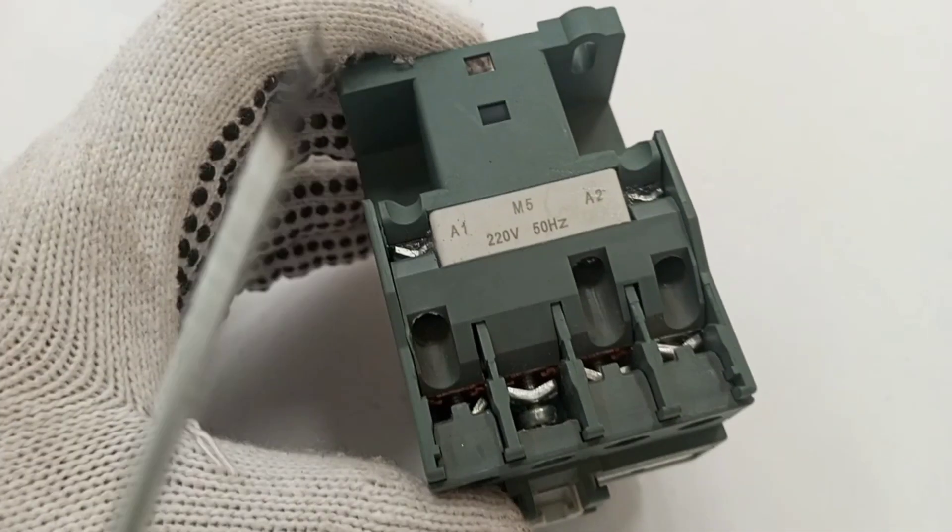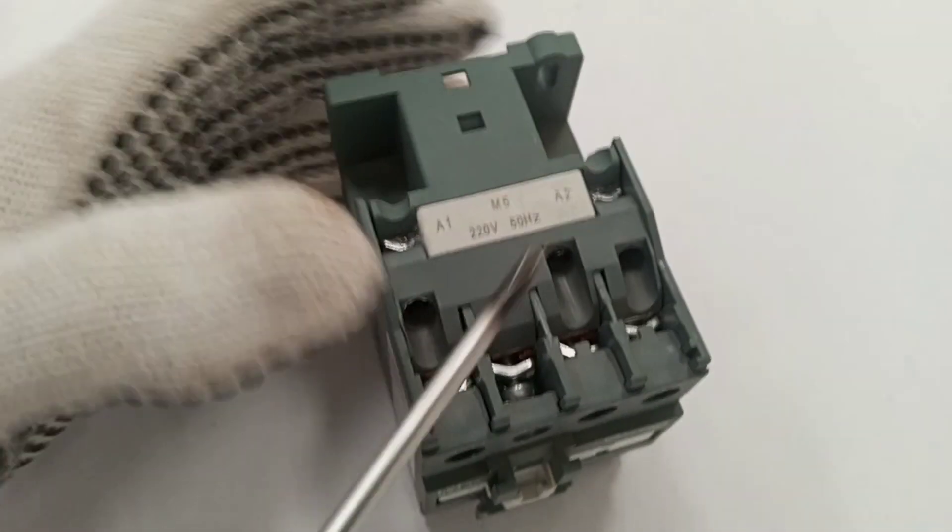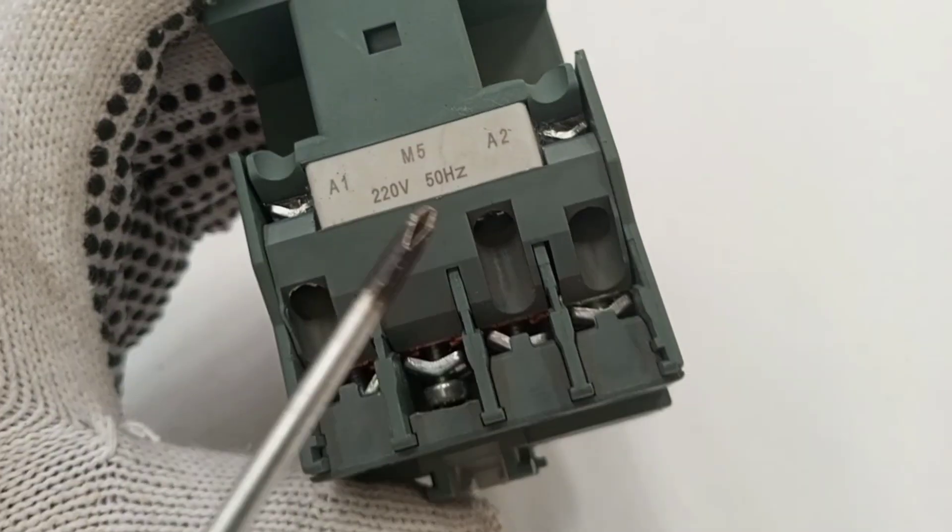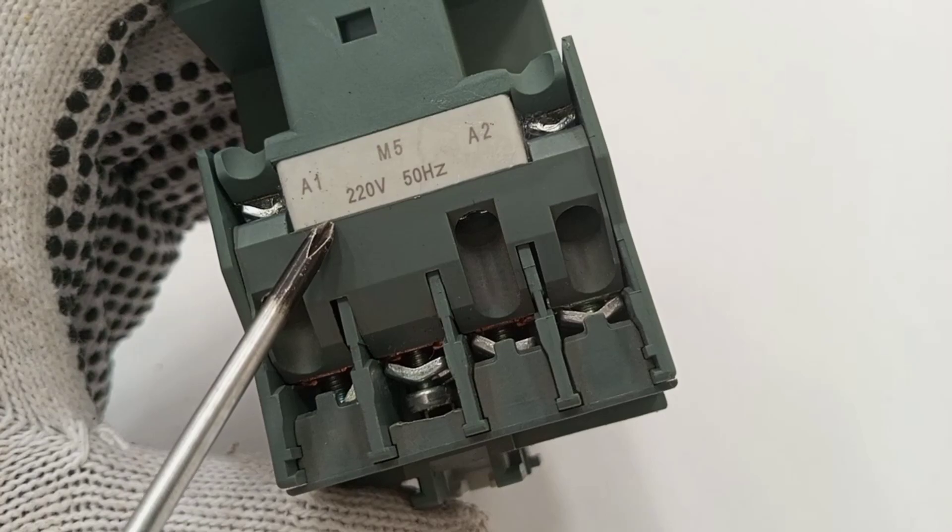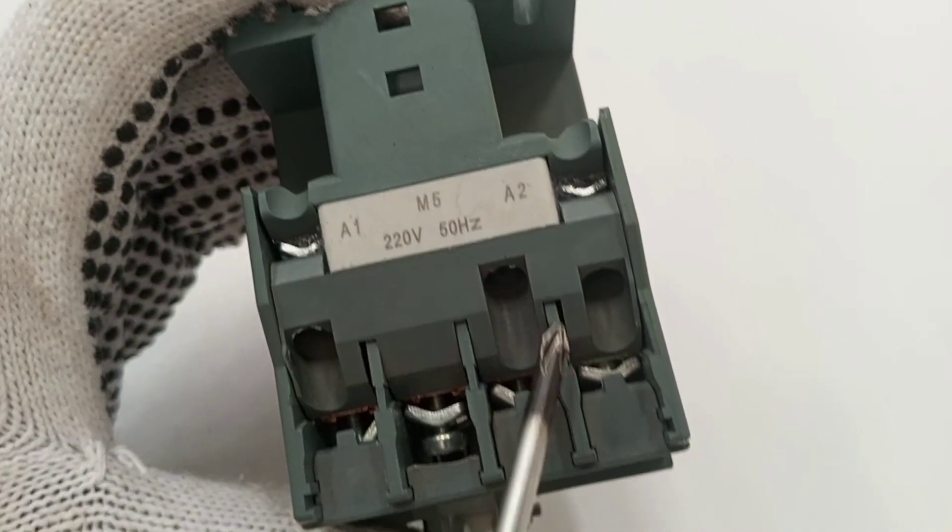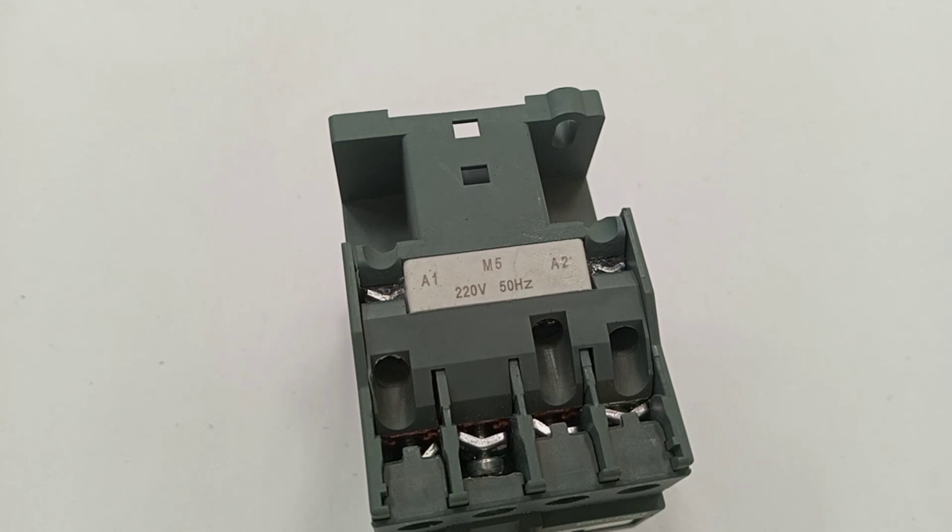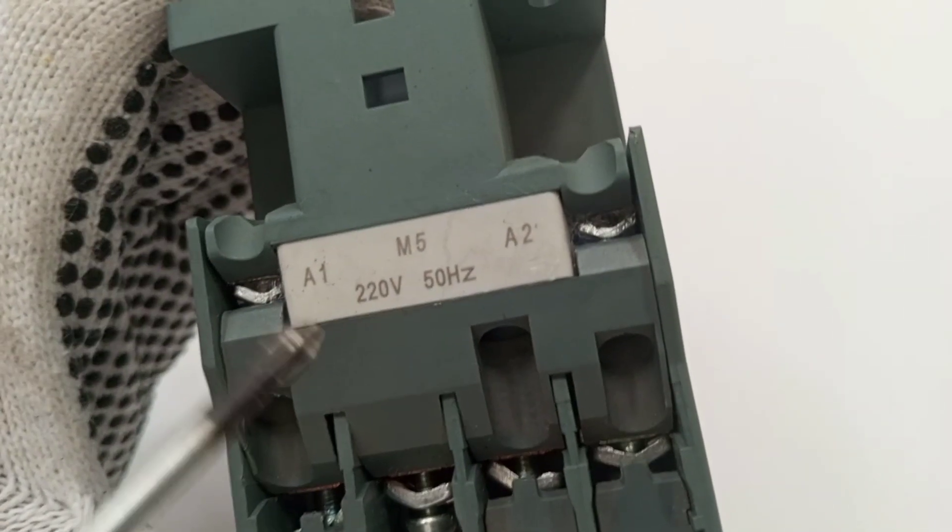There is no one standard voltage for contactor coils. The contactor coil can be designed to work on 220 volts like this one, but there are others that work on 120 volts and 400 volts AC. There are also contactor coils that will only work on 12 volts DC, and there are others that work on 24 volts DC.